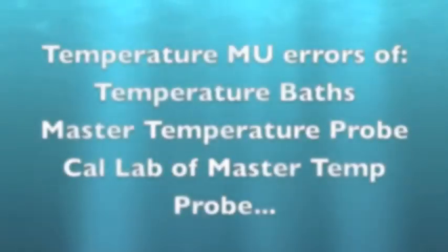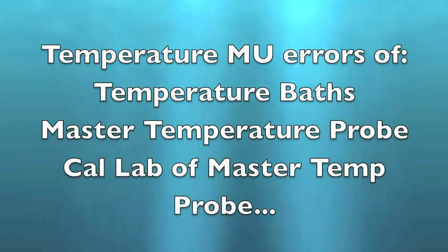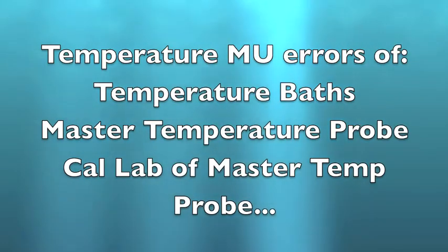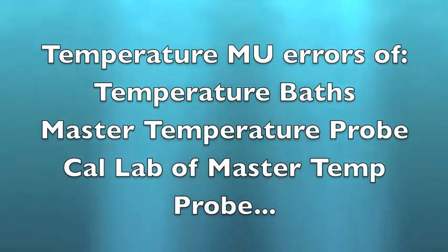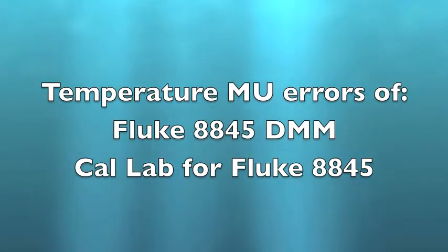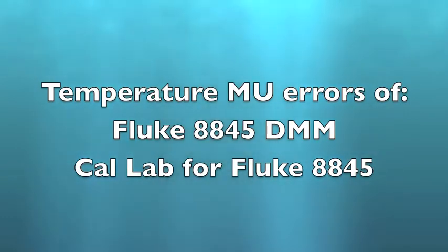Let's look at the temperature measurement uncertainty. It will include the errors from the temperature baths used for calibrations, the master temperature probe that's used, the cal laboratory for the master temperature probe, as well as the Fluke 8845 multimeter used in the calibration, and the errors from the cal laboratory that calibrated the Fluke 8845.